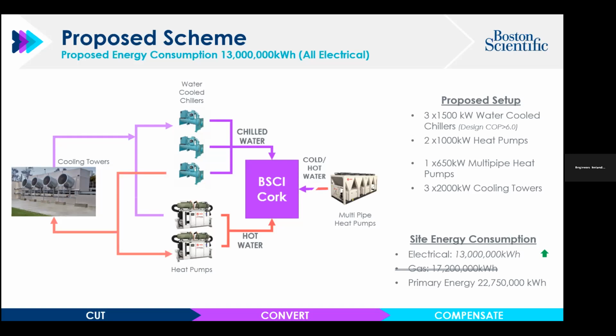And we'll use the cooling towers then. Again, the cooling towers are harvesting heat from the heat pumps and feeding water to the cooling tower to the water to water chillers as well. So that's effectively taking gas, no gas on site, it's all electric power. The electricity goes up, the 17,000 or 17 gigawatt hours of gas goes away, electricity goes up to 13 gigawatt hours. The overall primary energy is reduced from 29 to 22 gigawatt hours.